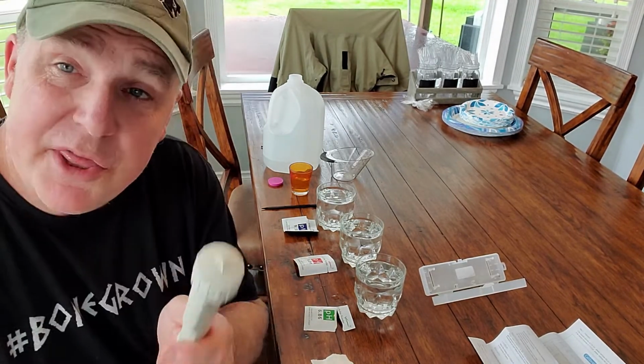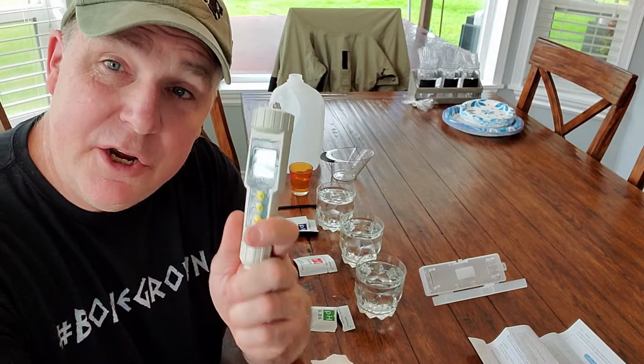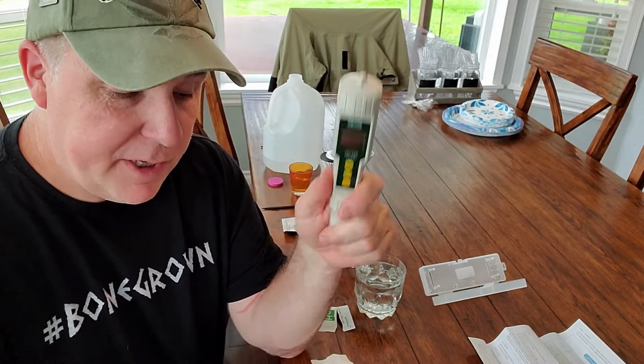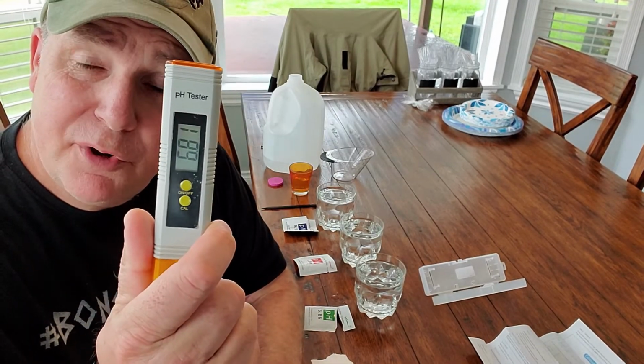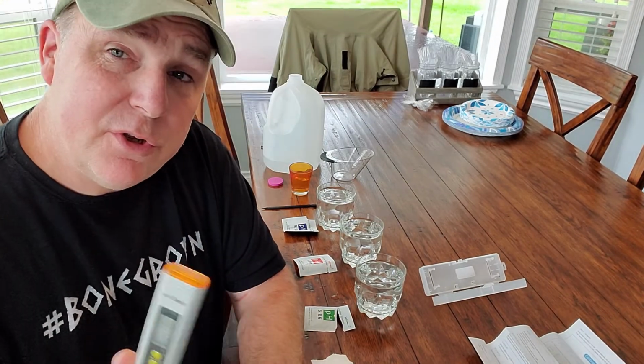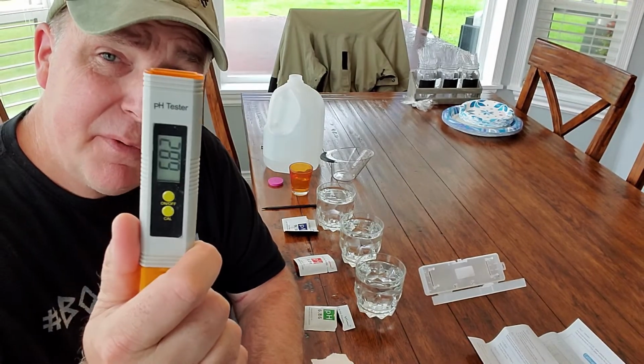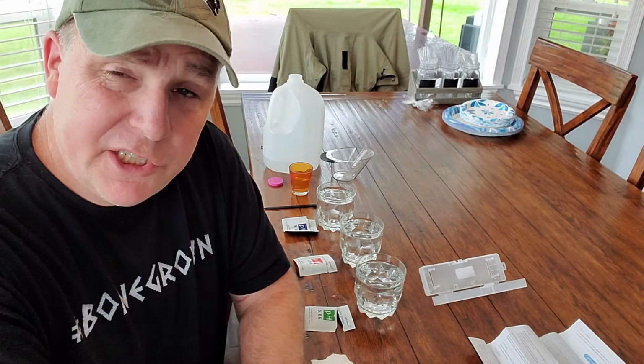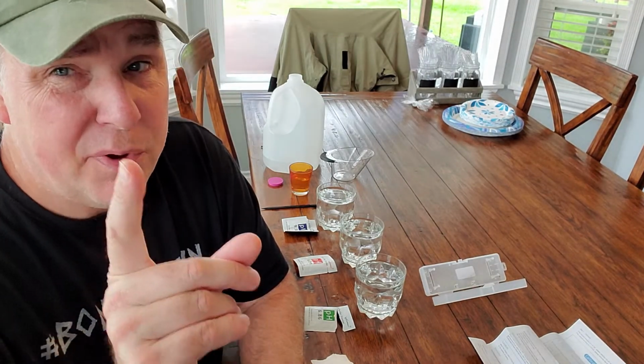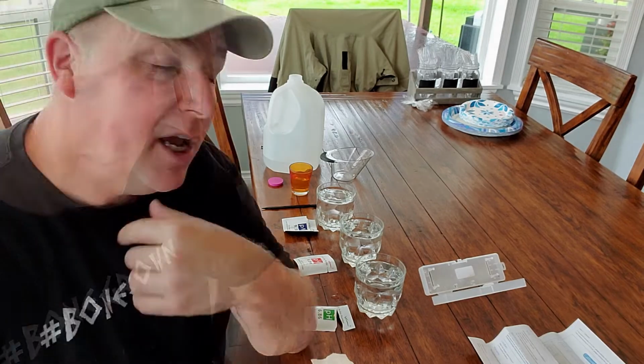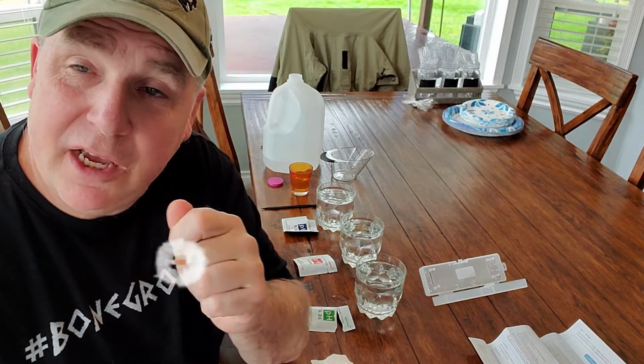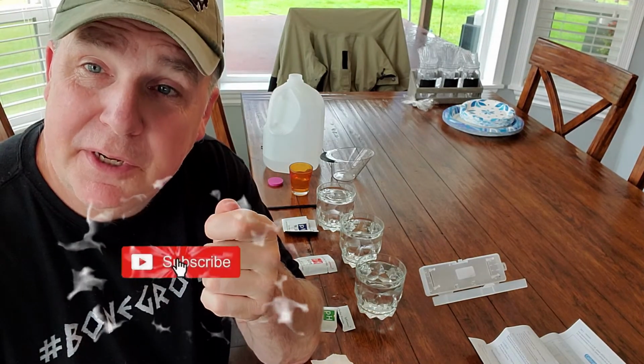And that's how you calibrate a new pH meter or recalibrate your existing pH meter. If you need to, go online and get some of the pH testing kits just so you have them around. It's better to be safe than sorry. And I hope this helps you out with calibrating your pH meters and makes it just a little bit easier.